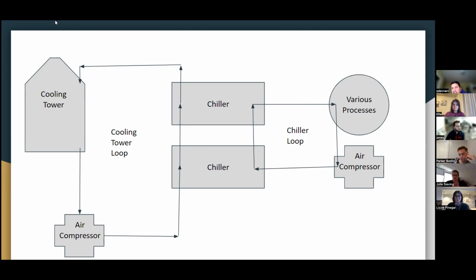And then there's cost, especially if it's glycol. Let's say you lost 200 gallons of water in this loop and 30% of it's glycol. Well, you've got to buy 60 gallons of glycol now, 30% of 200. So there's cost associated with just cutting this that could come with the water that may be lost in the process. Knowing whether it's water or a 30% glycol solution is important, because if it's water, it's easy, it's cheap. If it's glycol, that starts to add some cost to be accounted for.